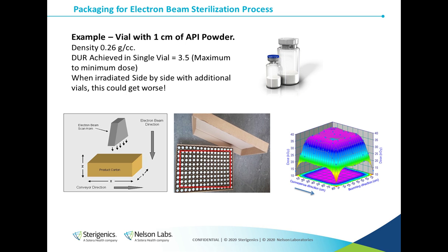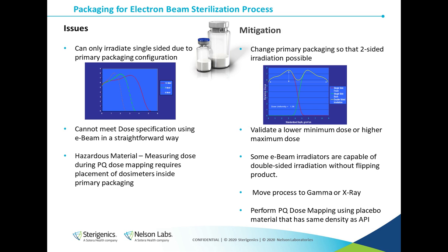After irradiating a single vial from one side, we achieved a DUR of 3.5. This could be problematic if the product specifications required a DUR of 2.0 or even less, for instance. There would also likely be an even worse DUR achieved if we irradiated the vials grouped together in a box, like that depicted at the bottom center of the slide. There are edge effects that can impact the vials at the side of the box in E-beam, and that might require that the vials in the box outlined in red would need to be dummy or placebo product instead of the active pharmaceutical ingredient.